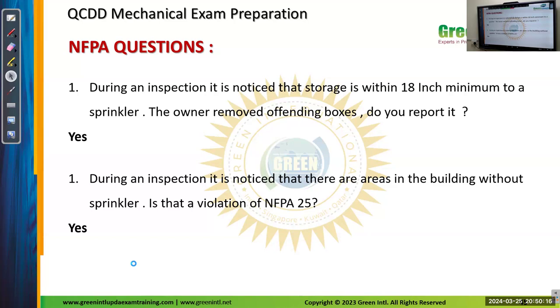During an inspection, it is noted that there are areas in the building without sprinklers. Is that a violation of NFPA 25? No, actually, it is not a violation of NFPA 25, because this area needs a sprinkler. That is a fault of design. The main purpose of NFPA 25 is to find whether the sprinkler is functioning or not. It is a violation of NFPA 13 or design. The answer is no. It is not a violation of NFPA 25.